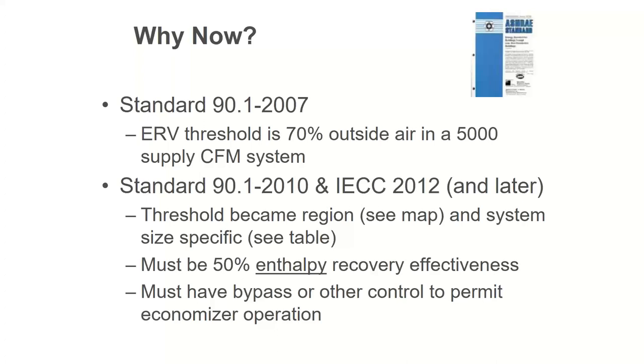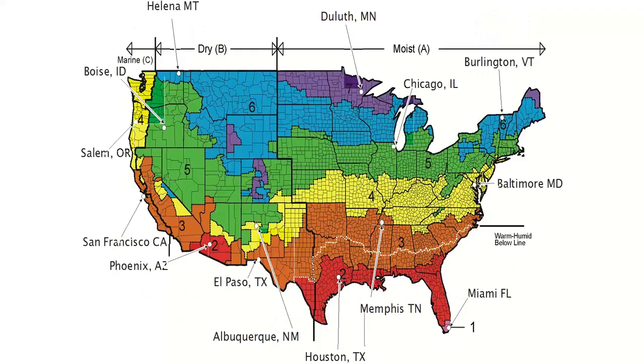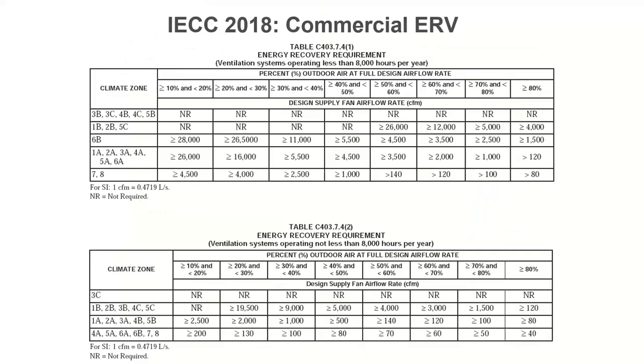The other big requirement in that regard is that we no longer look at 70% as the threshold. We get tables based on your geographic region. Most of you are in Chicago or Wisconsin. So Chicago is climate zone 5A. Wisconsin is 6A. You probably already knew that. When I go look at the tables, there are now two tables. There's the regular table on top, and then the bottom table is for 24/7 operation. So if it's a regular building where I don't operate all the time, and I look at climate zone 5A or 6A, where most of you are, this is my threshold.